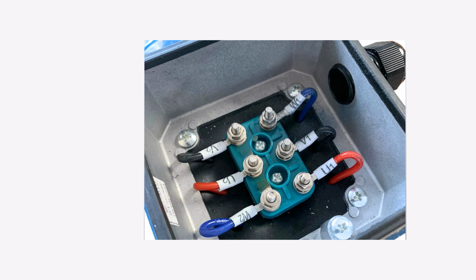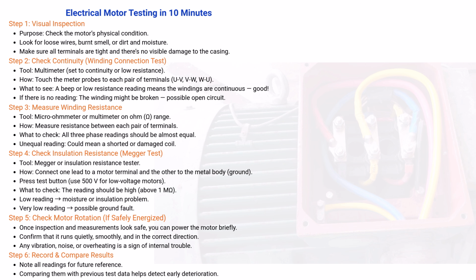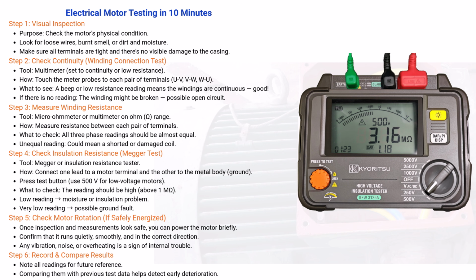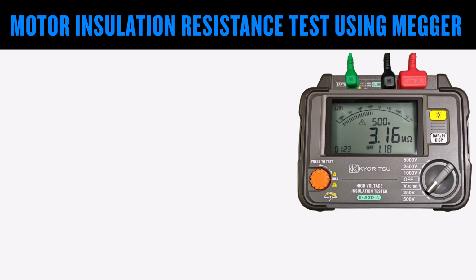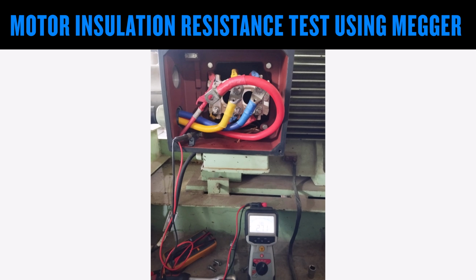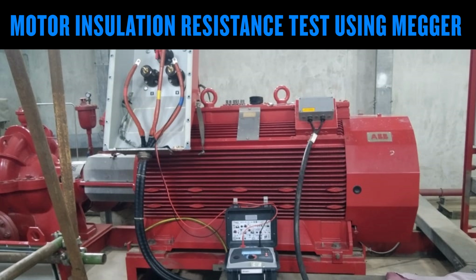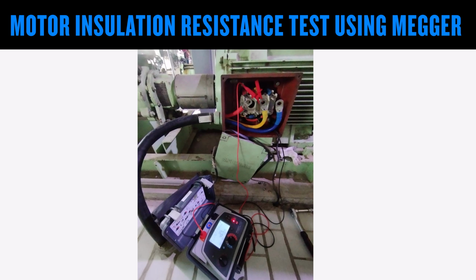After that, perform the insulation resistance test to confirm that the motor's insulation is in good condition, following the test procedure I shared with you. For insulation resistance test, use a Megger tester. Connect one probe to the motor terminal and the other to the motor frame. Press the test button and check the reading. A high resistance value means the insulation is healthy, while a low reading indicates moisture or insulation damage that needs attention.